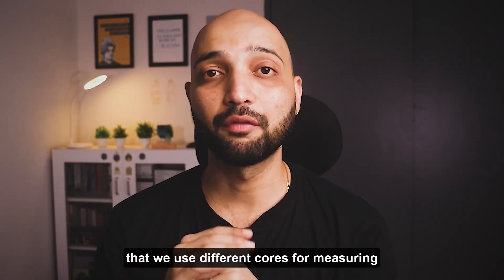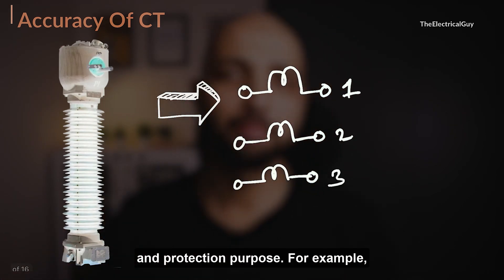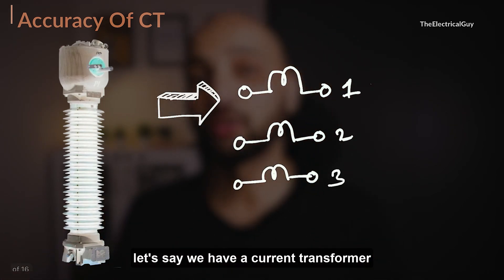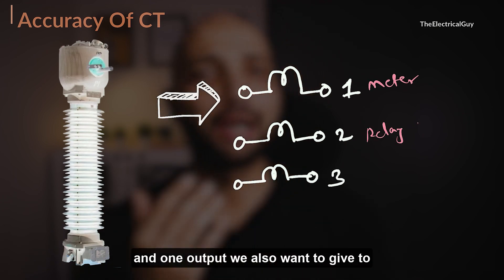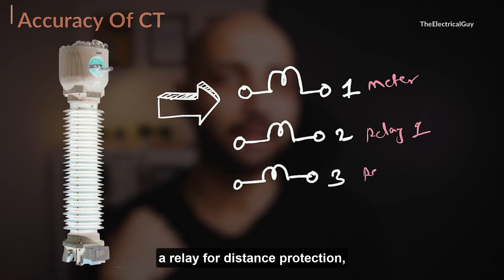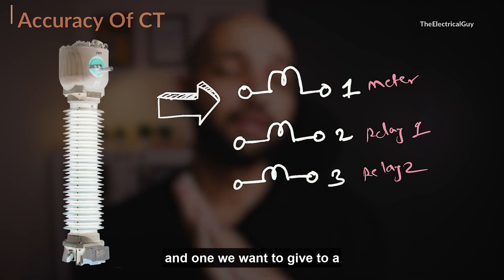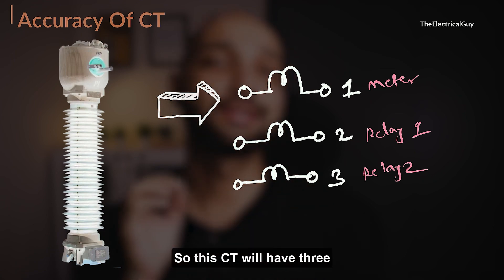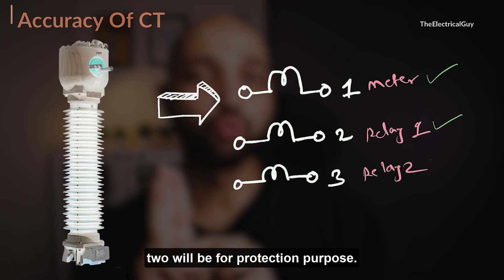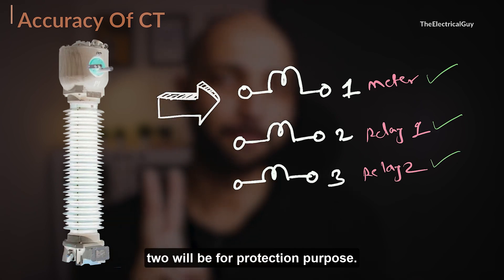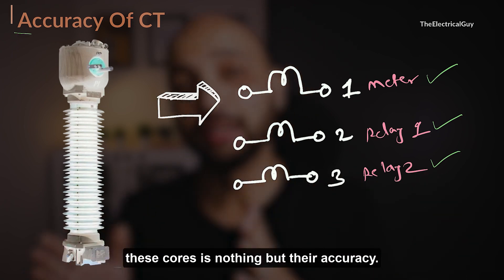The first thing to keep in mind is that we use different cores for measuring and protection purposes. For example, a current transformer might have one output going to a meter to measure current, one output going to a relay for distance protection, and one going to a differential protection relay. So this CT will have three different cores — one dedicated for measurement and two for protection — and what creates the difference between these cores is their accuracy.